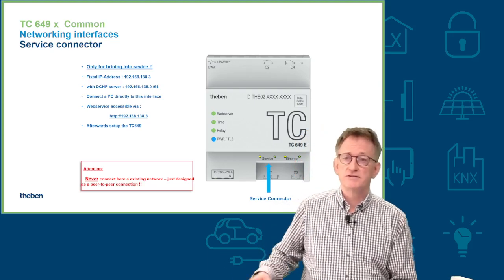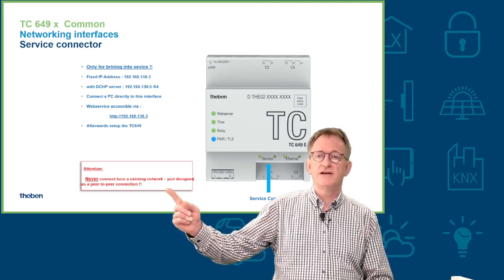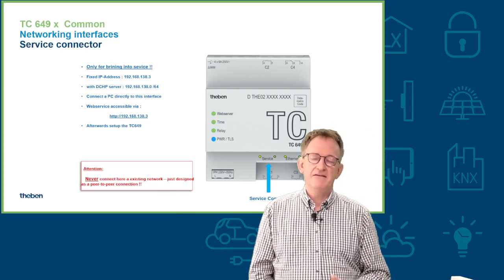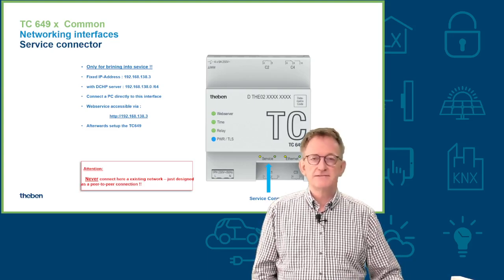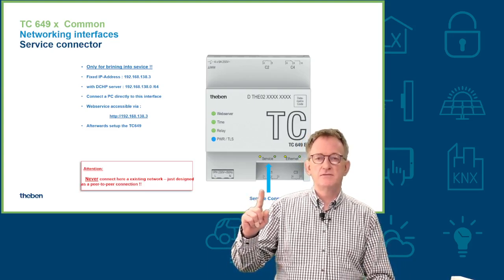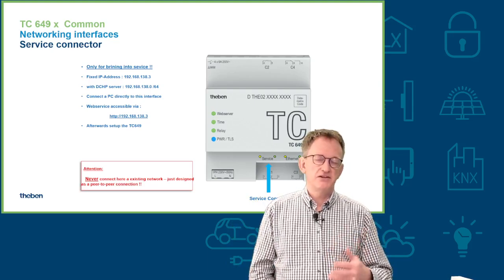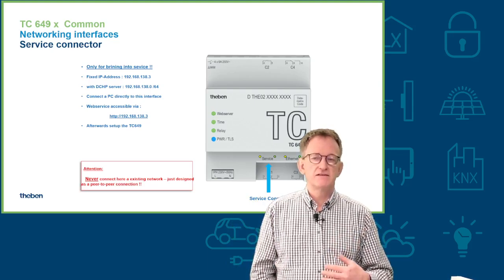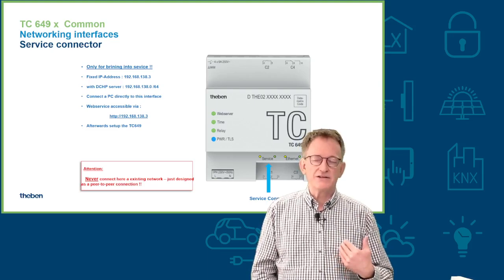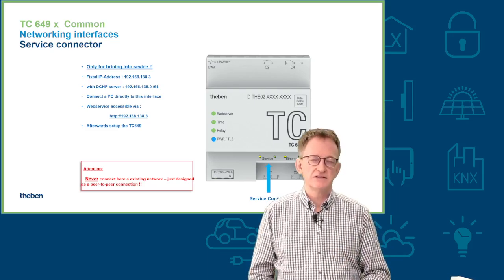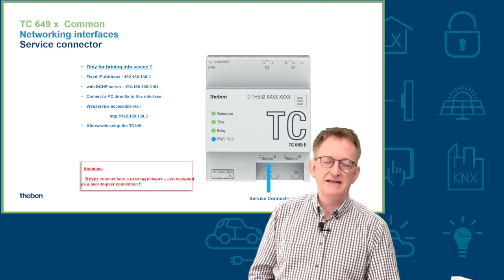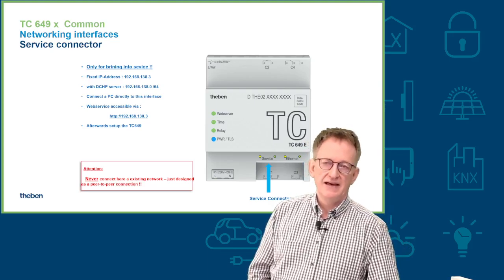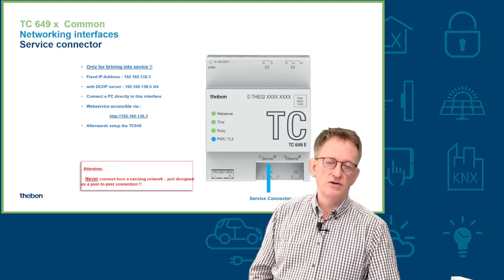Very, very important, and I have marked it here in red. Please never ever connect that service connector, this one here, to an established network. That's not the intention, and that's also not allowed, because there is also a DHCP service running on that device, and you do not want to have that service available in your intranet.